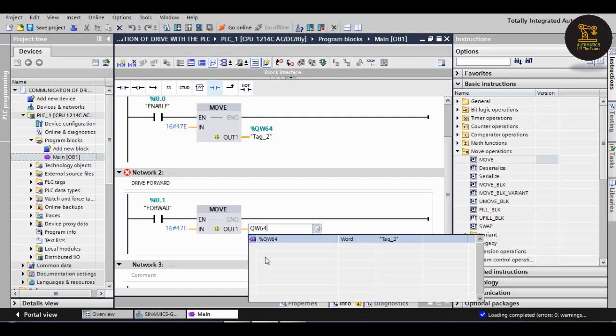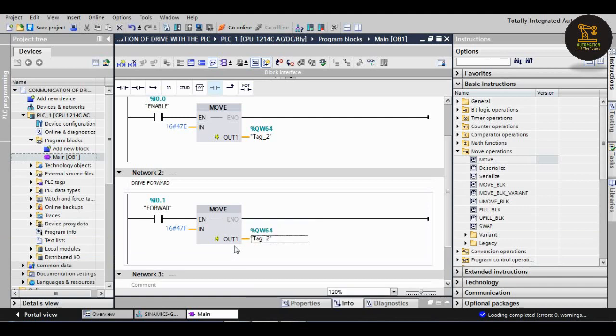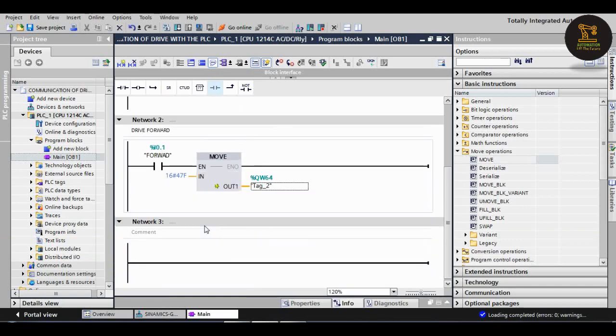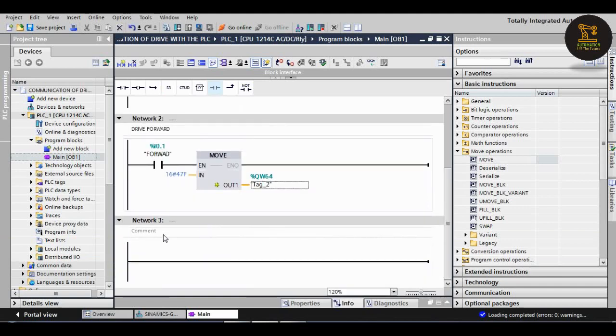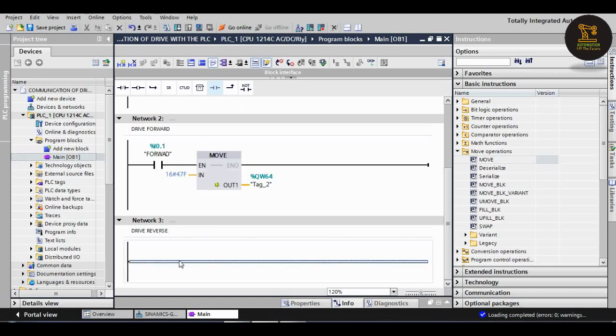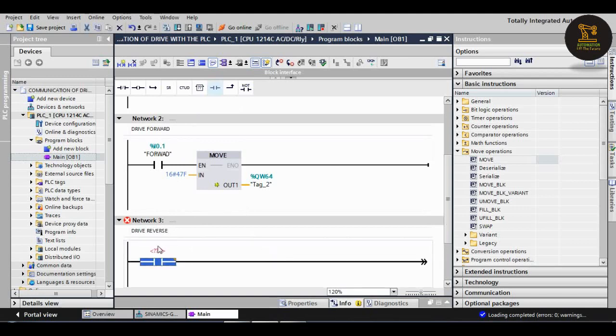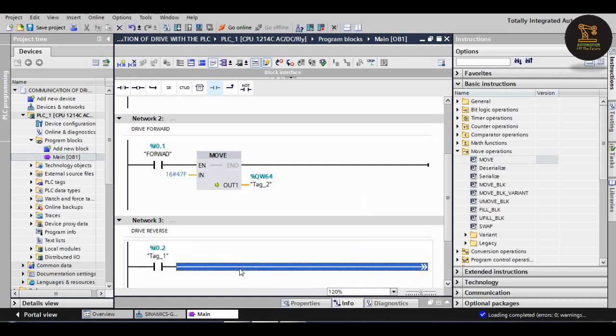Next, for drive reverse. Again I am taking the switch, normally open, which is I0.2. Again I am taking another move block.